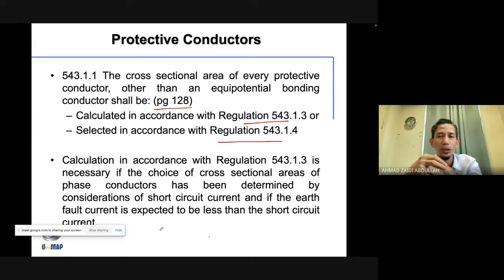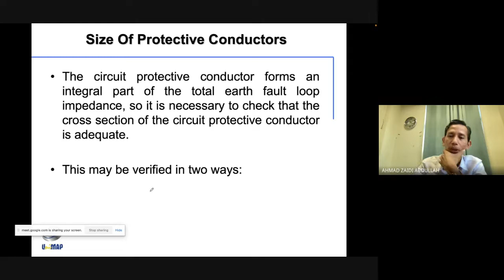Okay. So calculation in accordance with a regulation is necessary if the choice of cross-sectional area of a phase conductor has been determined by consideration of short circuit current and if the earth fault current is expected to be less than the short circuit current. So this one is based on the calculation of short circuit lah. Okay, short circuit current, kalau kita tahu lah. Okay, the circuit protective conductor forms an integral part of the total earth fault loop impedance. So it's necessary to check that cross section of a CPC is adequate. So it must be verified in two ways. Ada dua cara lah.